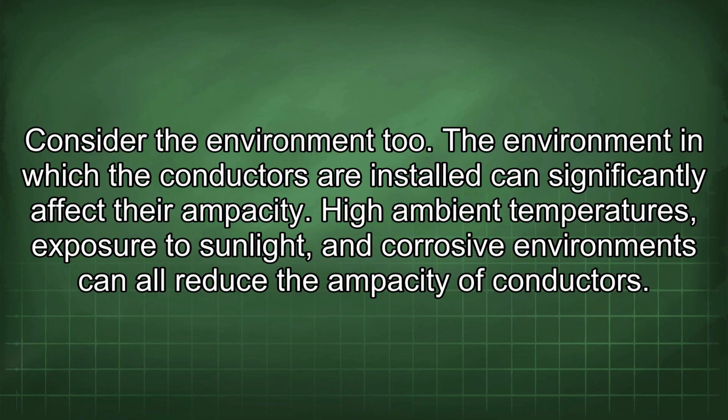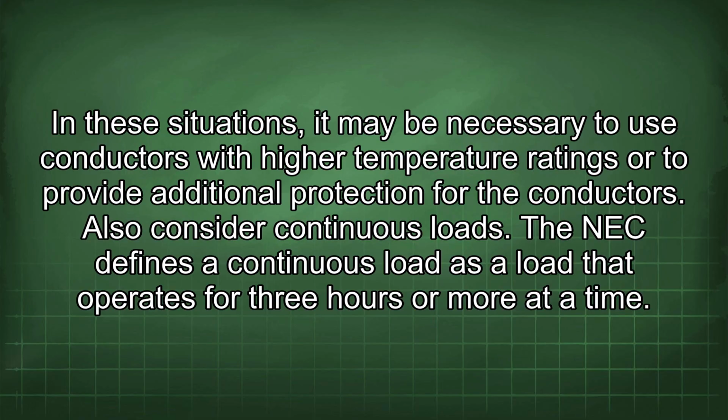Consider the environment too. The environment in which the conductors are installed can significantly affect their ampacity. High ambient temperatures, exposure to sunlight, and corrosive environments can all reduce the ampacity of conductors. In these situations, it may be necessary to use conductors with higher temperature ratings or to provide additional protection for the conductors. Also consider continuous loads.